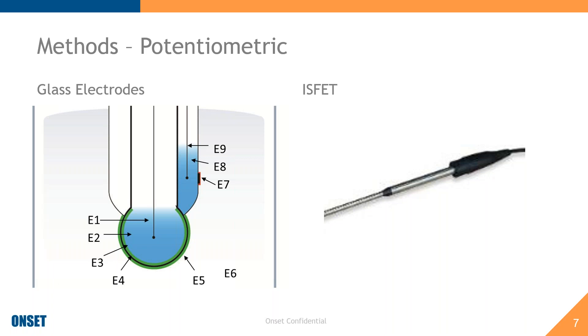ONSET uses a glass bulb electrode, which makes our pH logger suitable for many applications requiring good accuracy, short hysteresis — meaning it responds quickly to changes in pH — and faster acclimation compared to ISFET-type loggers.